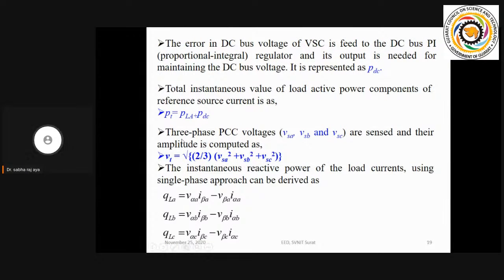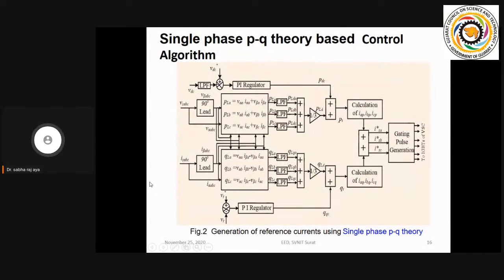Okay. Then again, a main point: why do we want to add this? Generally, the output of the DC bus PI acts as the loss component of the voltage source converter. Again, the main thing: the output of the DC bus PI acts as the loss component of the voltage source converter. So simply you can add the loss component. Again, in the lower loop, the AC bus loop, from whatever reactive component you are getting from the PI loop, you can subtract the load reactive component.